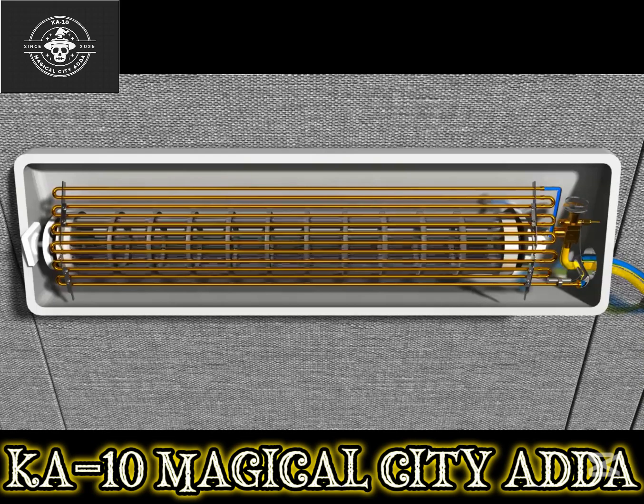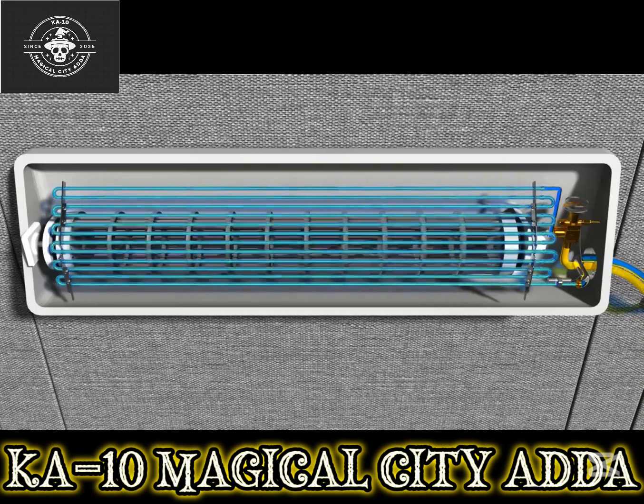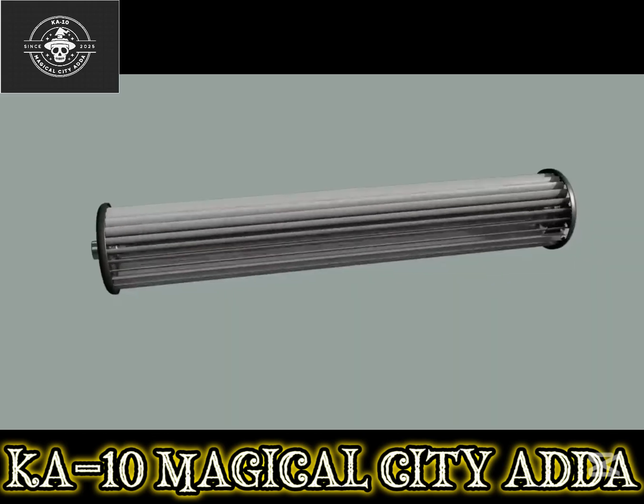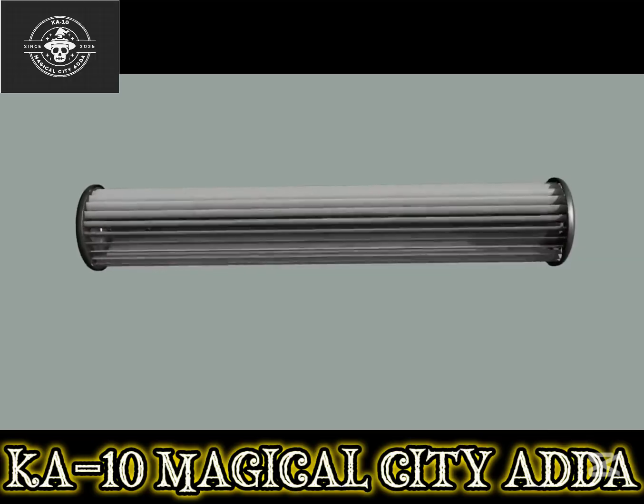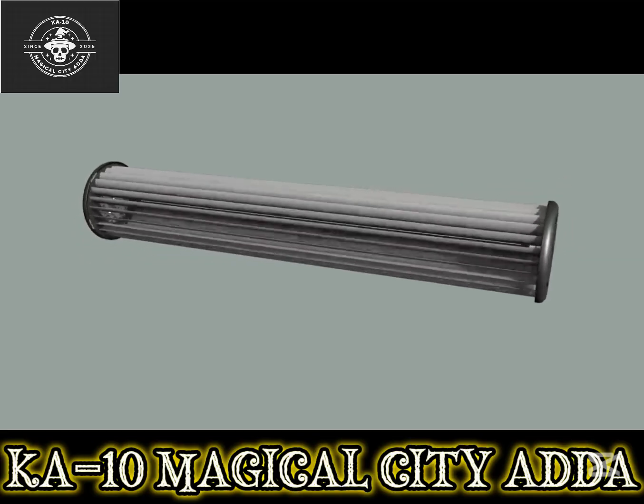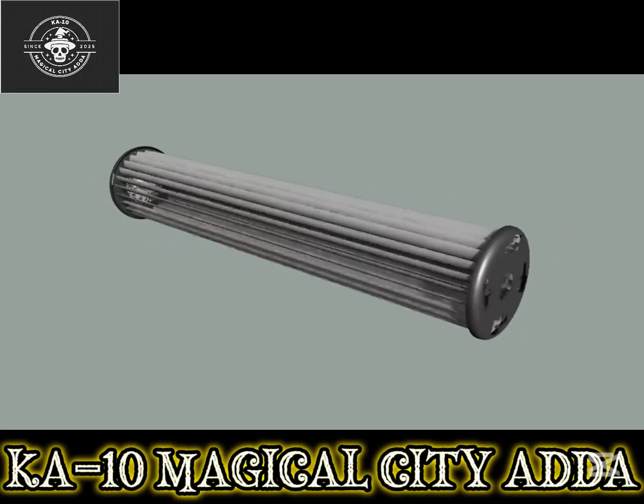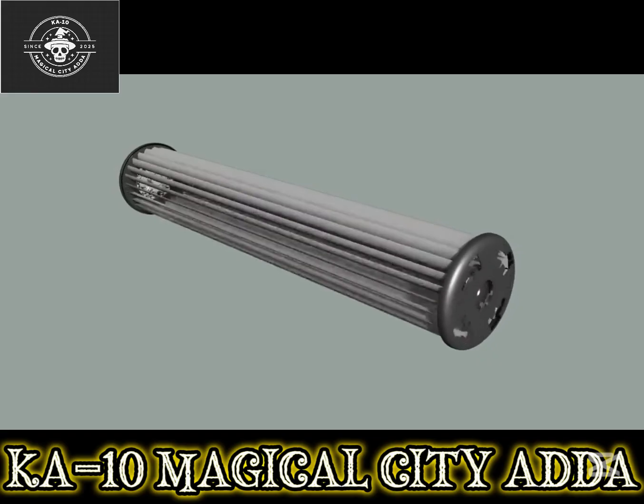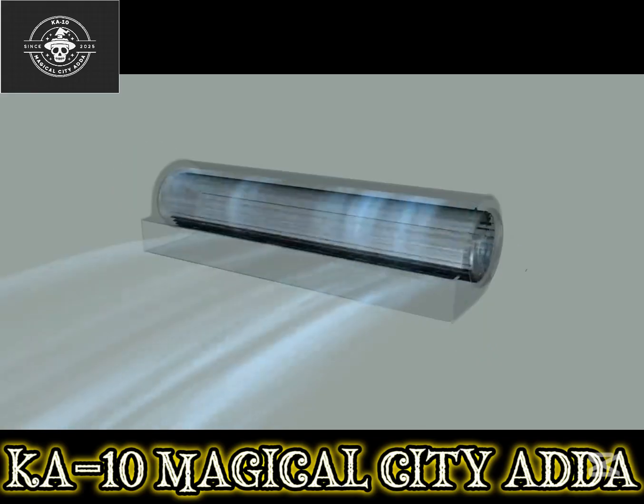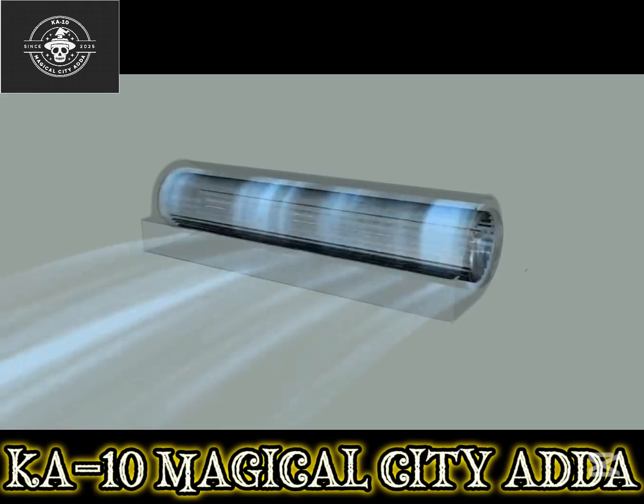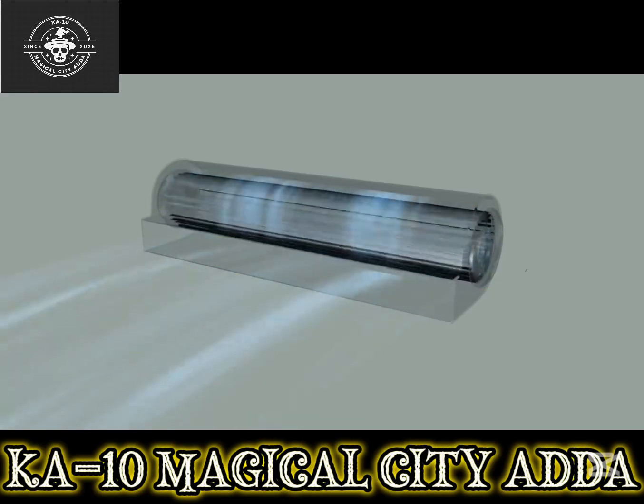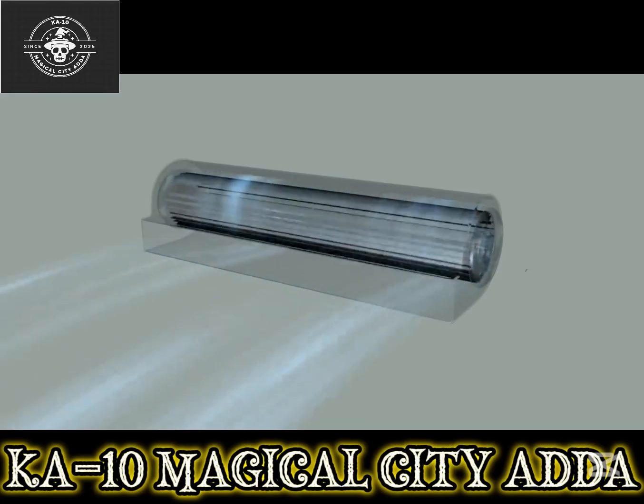A refrigerant passes through the pipes of an evaporator and takes away heat in this process. As the fan underneath starts to operate, warm air in the room is sent to the evaporator and cooled air is emitted. Fans used in the indoor unit of an air conditioner are shaped as a cylinder rather than the more familiar version of a propeller. Such a type of fan is called an impeller. As wall-mounted air conditioners cannot take up large space, impeller type of fan is used instead of propeller type.